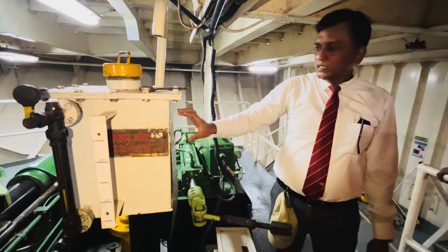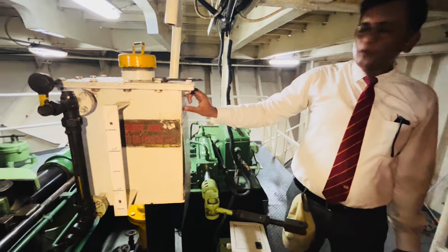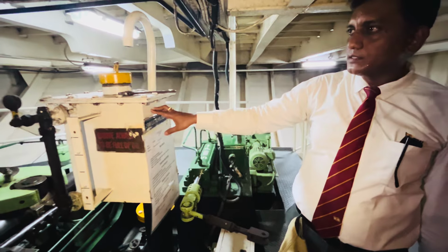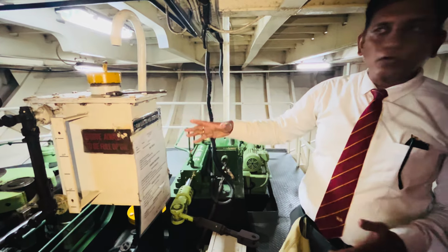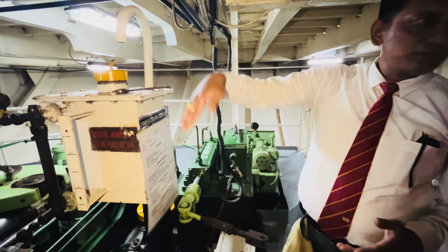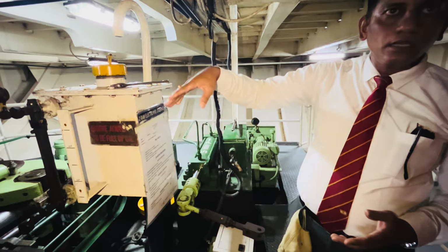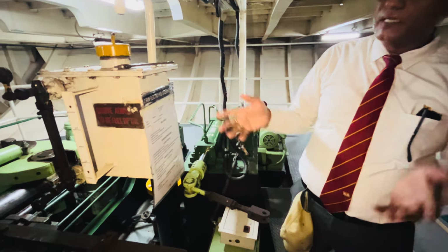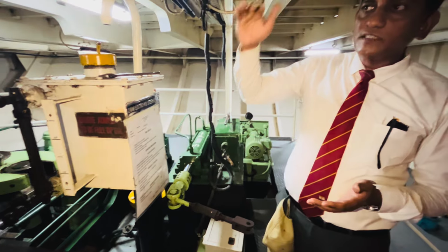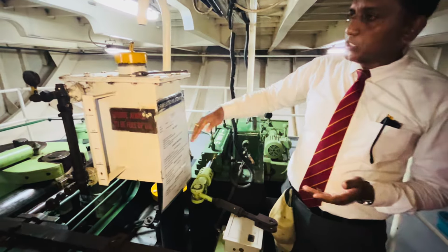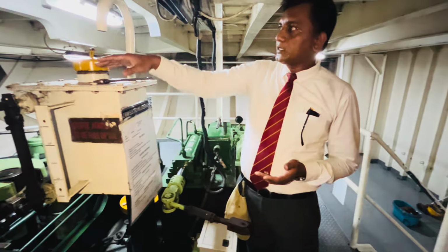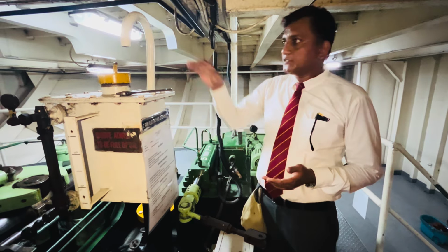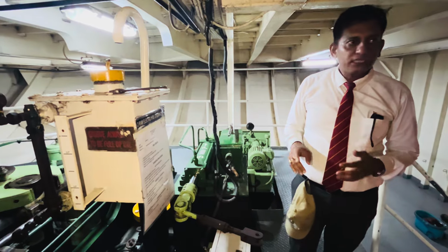Suppose the oil is here. At the top there is a space between the oil and the tank. Suppose the oil is hot. What will happen to the air? The air will get expelled out because it is hot. Once the hot air is removed, the oil will become cool, and the cool oil will settle down. When it settles down, it will take new air, so it will take suction. Hot air goes out and cold air comes in. That is why it is called a breather.